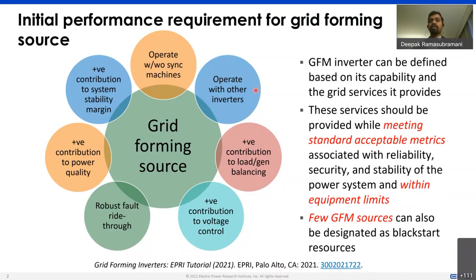It can operate with other inverters, provides positive contribution to load generation balancing, positive contribution to voltage control, has robust fault ride-through, provides contribution to system stability margin, and provides a positive contribution to power quality. And it has to be capable of doing all of this while meeting its equipment limits and while also meeting acceptable metrics that we have from a system reliability perspective.